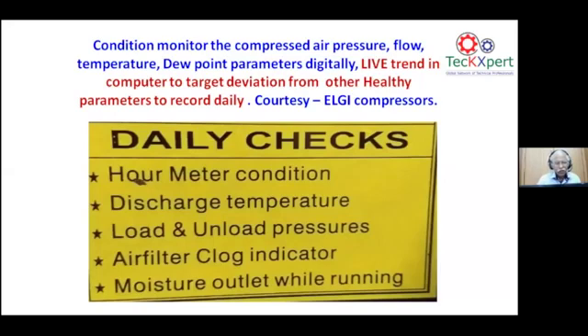Many of the compressor OEMs have to give a serious thought to it, especially in Indian conditions, where the SPM, or suspended particulate matter in the air, is very high, the dust is more, and the clogging is more. Definitely all the compressor OEMs have to give serious thought and see to it that air filter clogging is not allowed in the existing compressor and that it is monitored.